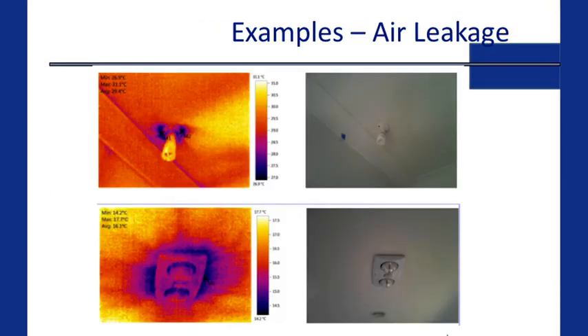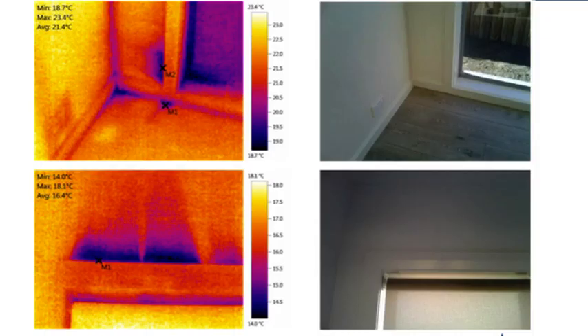Other examples of air leakage: the image on the left shows a bayonet fitting with what looks like water spraying out all around it. Pretty typical — we drill a large hole in the ceiling and poke a cable through it, and if you multiply that by 50, you've got a big hole in the house. Exhaust fans also show leakage through them — the current code doesn't require us to seal them to non-habitable areas, providing a large ventilation area in bathrooms and en suites. Bottom plates show leakage from the architrave. Most leakage comes from the bottom of the building, so it's really important to seal up. We've also got air being drawn in across the top of window architraves — trades haven't been educated to caulk the horizontal ones because you can't see them, which comes back to education.